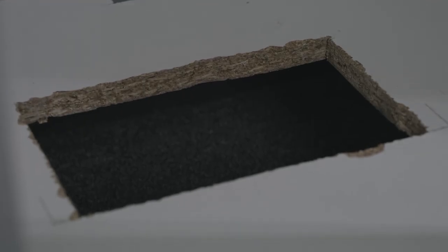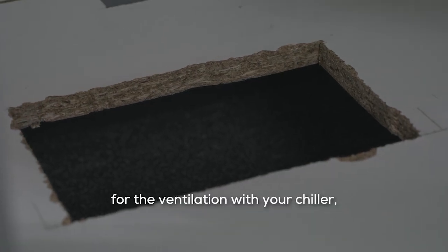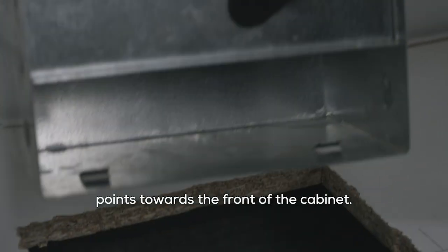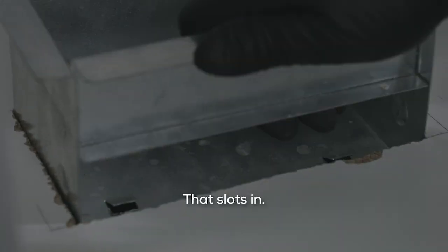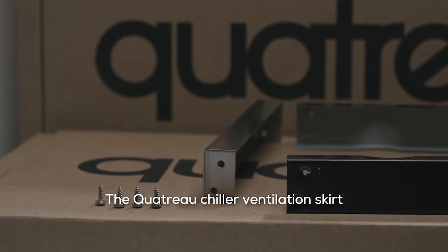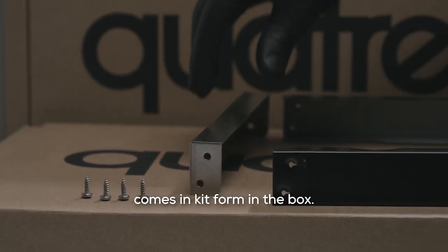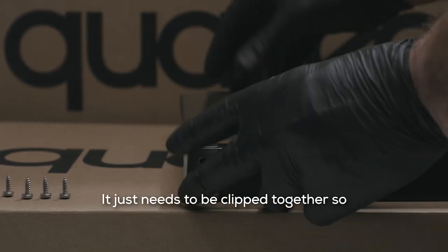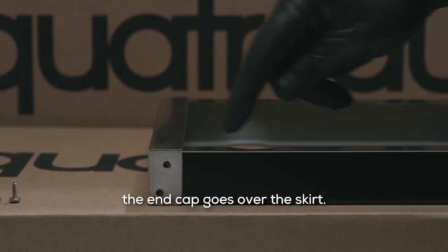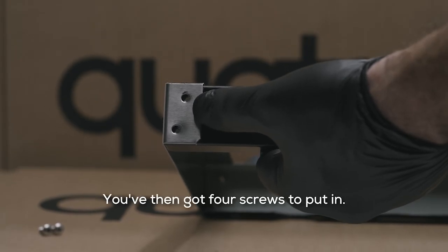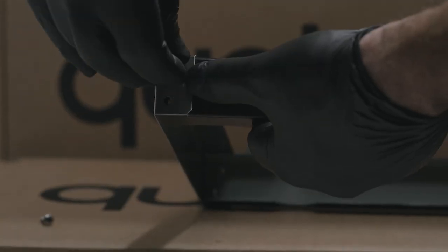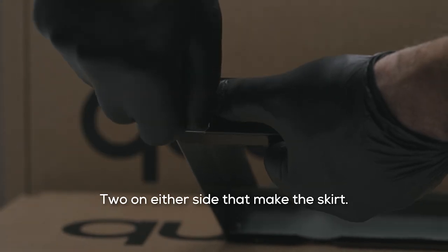Now that the hole has been cut, we can install the first part of the trunking for the ventilation for your chiller, making sure that the hole in the trunking points towards the front of the cabinet. That slots in. Should be nice and tight. And then the second part of the trunking clips into the front. The Quatreau chiller ventilation skirt comes in kit form in the box. It just needs to be clipped together so the end cap goes over the skirt. You've then got 4 screws to put in, 2 on either side, that'll make the skirt.